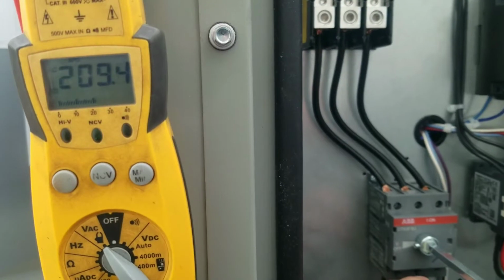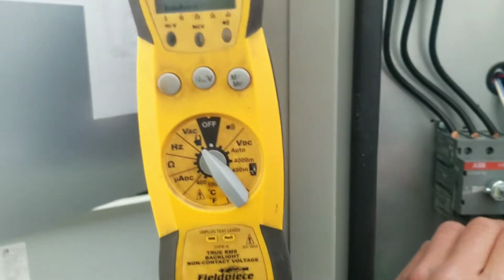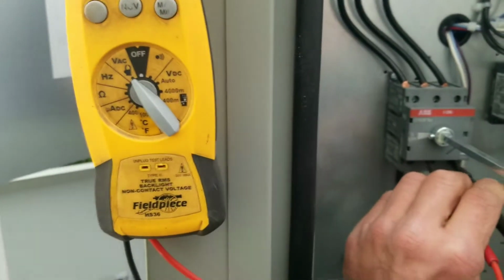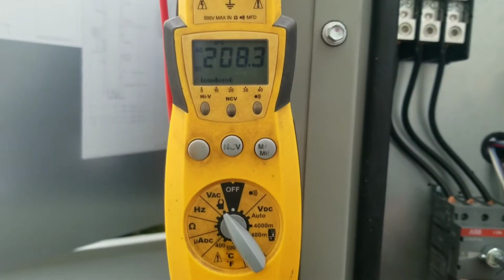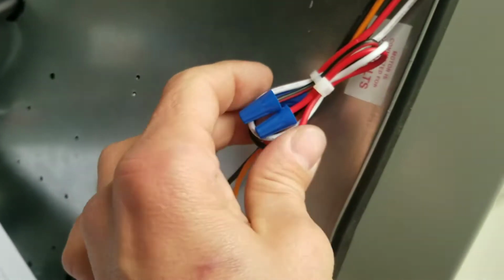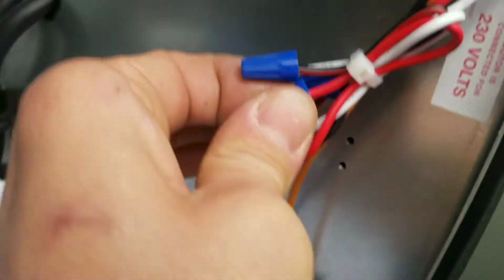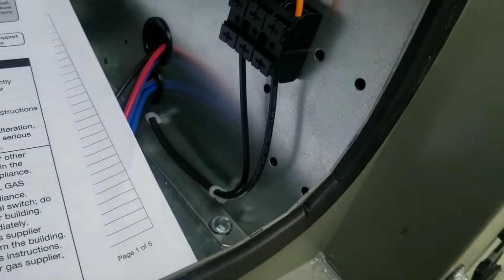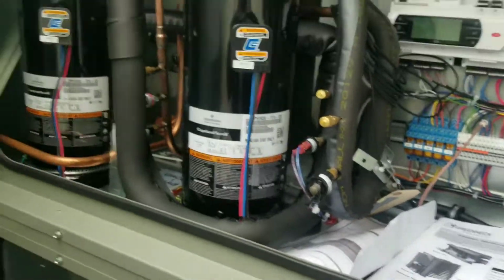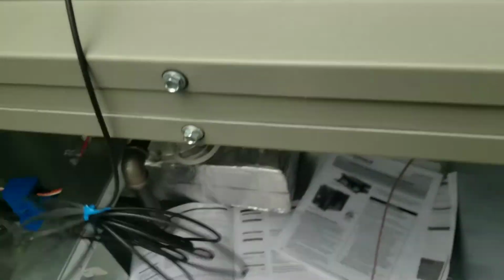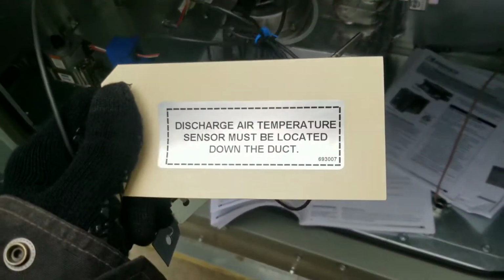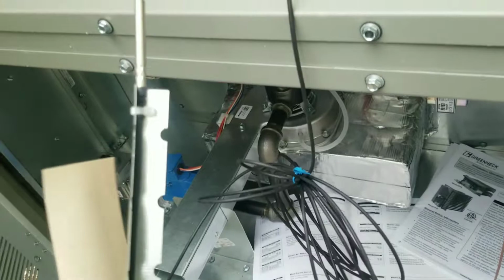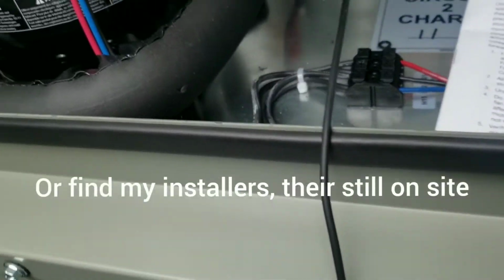We're just going to verify our 3-phase. I need to get me one of the new field pieces that can show me the phase rotation. Well, we got 208 volts. 208 is our red wire, and orange is 240, so we're going to correct that because that's wired wrong, and then we'll go from there. You would think these would come installed, but we're gonna, I guess, play installer too, not just startup guy.